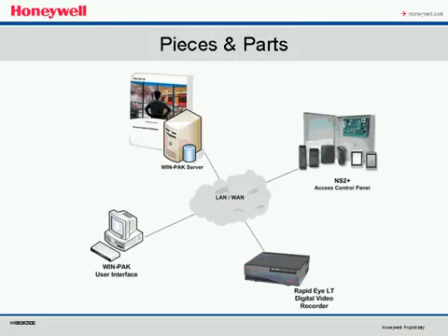I've had customers use input boards right now, specifically at a location in South Carolina. They've got a warehouse about three football fields long, and they're tying an input board in at the head end in the server room, and at another panel at each individual panel throughout the facility where the cameras are located. The connections are actually being made through the software instead of running the wire back and forth.